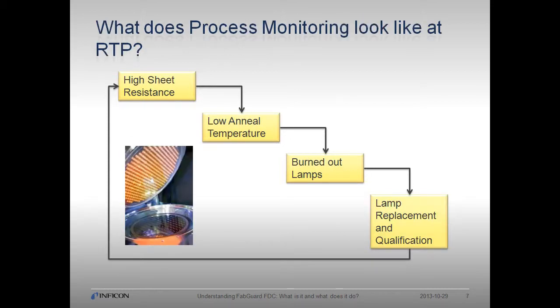Let me give you an example of process monitoring in your factory using an RTP tool. We've run a test wafer at RTP anneal, and the sheet resistance is high, as determined by our SPC chart. This usually happens when the dopant isn't sufficiently activated, and suspects that the temperature was low. Equipment maintenance discovers more than the allowable number of burned-out lamps. The lamps are replaced, and the RTP tool is qualified and returned to production.